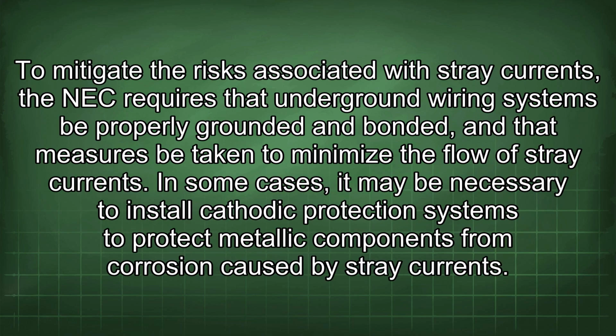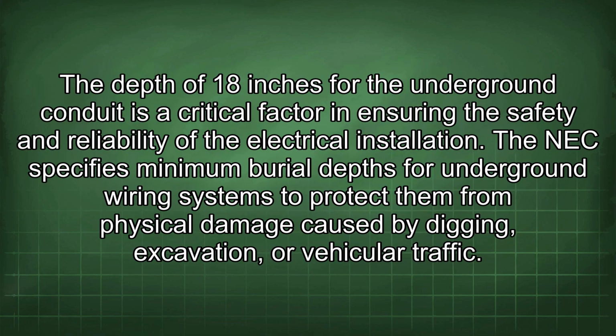To mitigate the risks associated with stray currents, the NEC requires that underground wiring systems be properly grounded and bonded, and that measures be taken to minimize the flow of stray currents. In some cases, it may be necessary to install cathodic protection systems to protect metallic components from corrosion caused by stray currents. The depth of 18 inches for the underground conduit is a critical factor in ensuring the safety and reliability of the electrical installation.